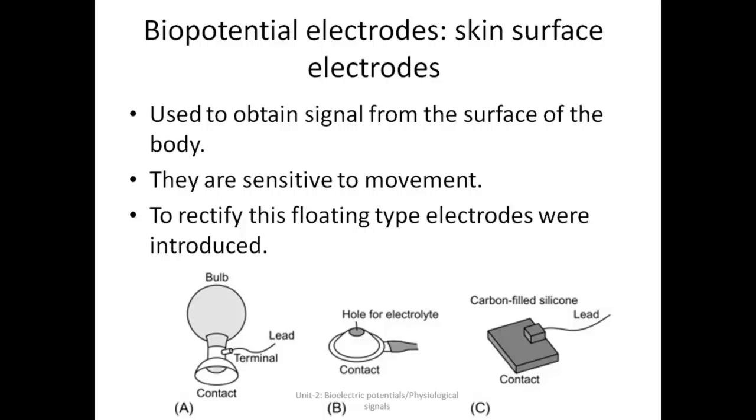Although any type of surface electrode can be used to sense ECG, EEG, or EMG potentials, the larger electrodes are usually associated with ECG, since localization of the measurement is not important in ECG, whereas the smaller electrodes are used in EEG and EMG measurements, because in EEG and EMG sometimes a very specific position is required while making the recording.